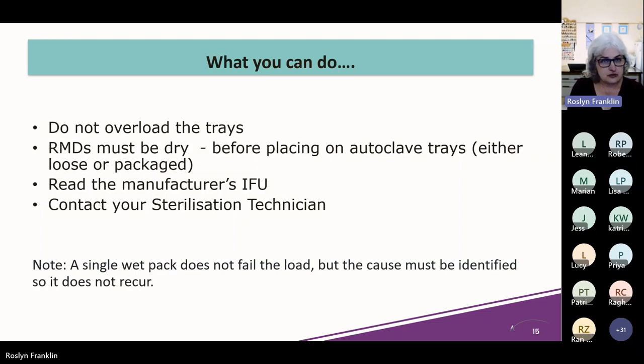Another thing too is, were the instruments dry before they went into the autoclave? I know when dental assistants are rapidly trying to get things through, they'll do the fast dry and package things while everything's still wet and damp. It's really important that everything in there is dry, because the water used in an autoclave cycle isn't good old tap water, it's filtered, demineralized water, and you don't want to upset the balance of water that's in there.